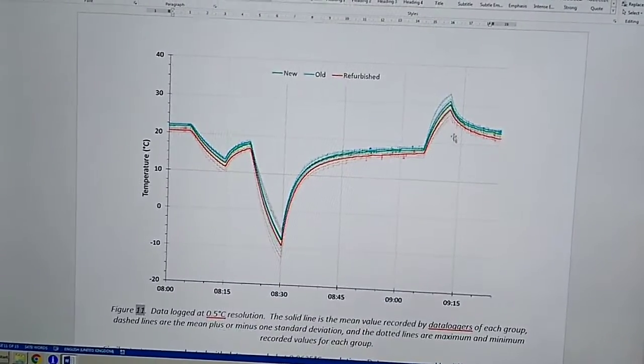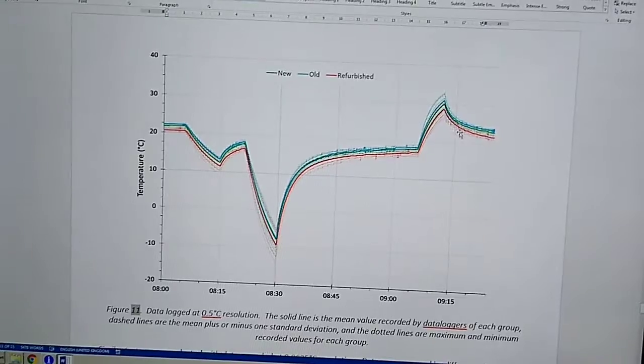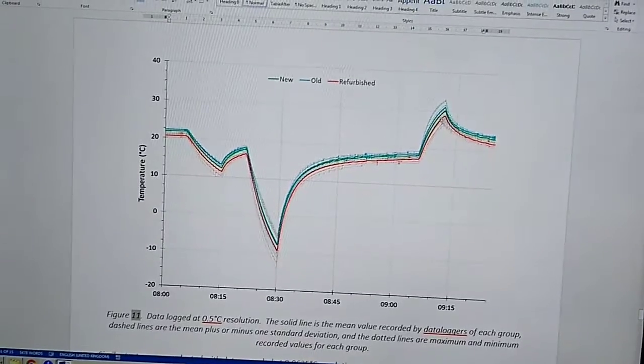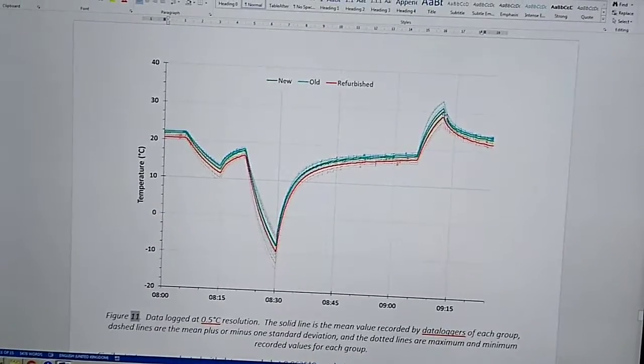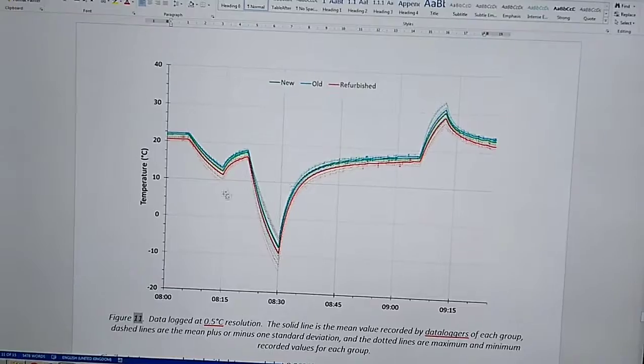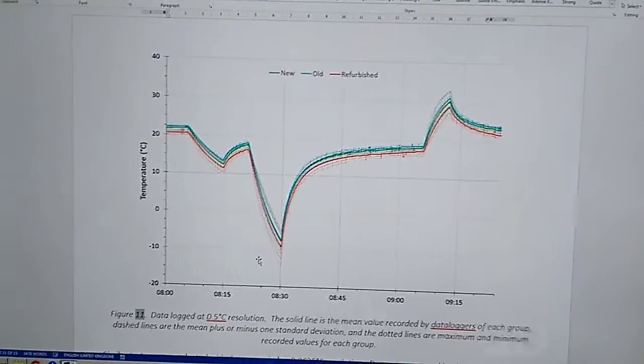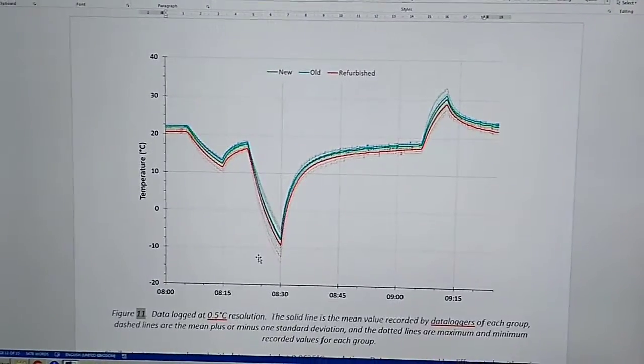which you can clearly see my refurbished i-buttons tend to slightly under read by maybe one degree compared to the mean of the new ones. That's logging at half degree C resolution.